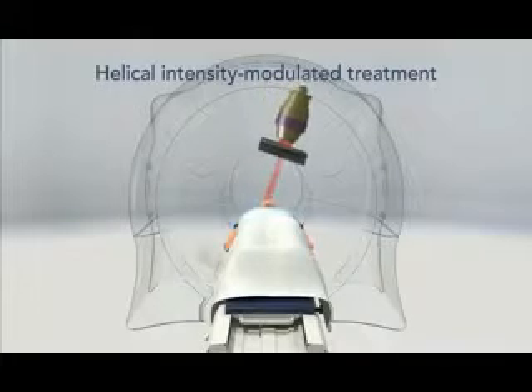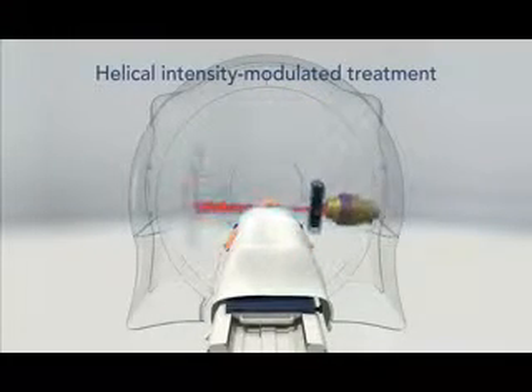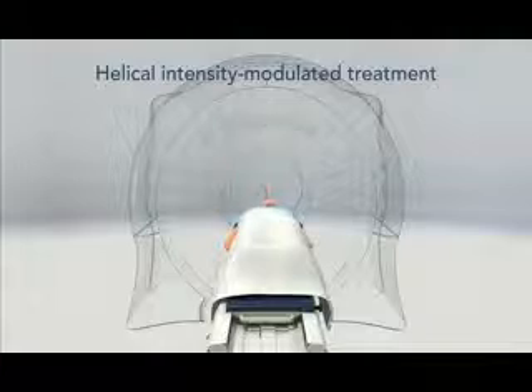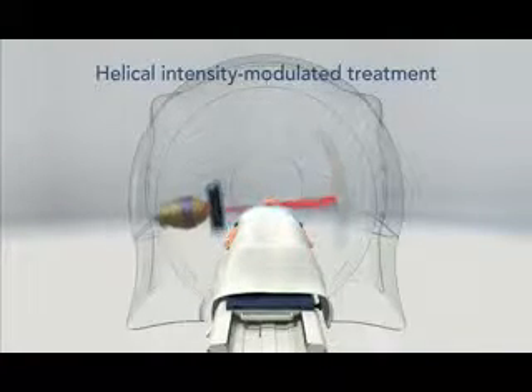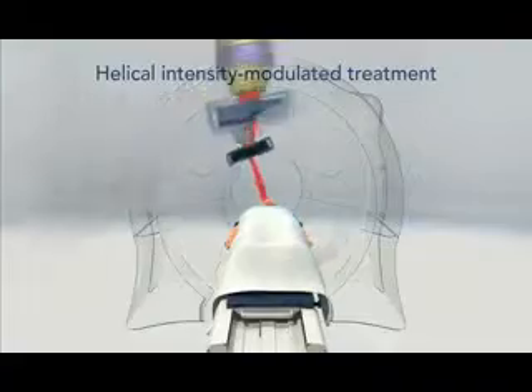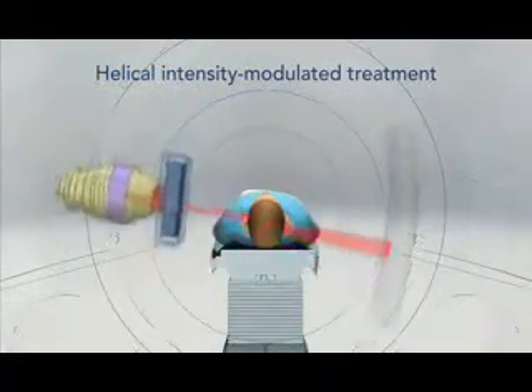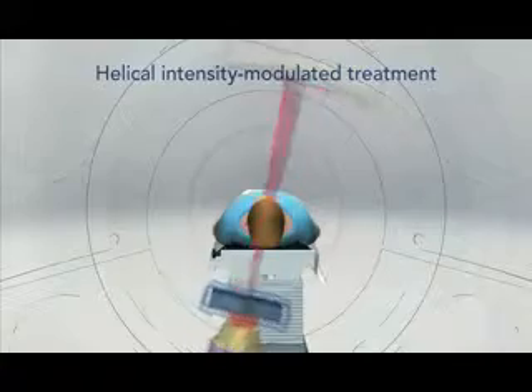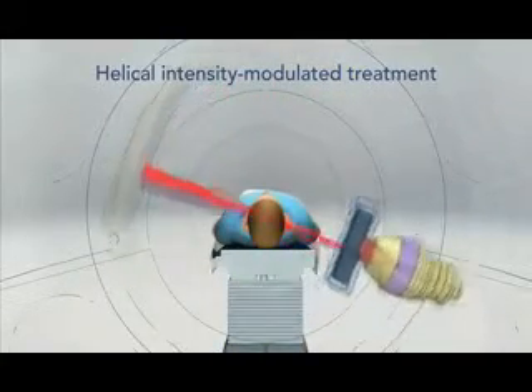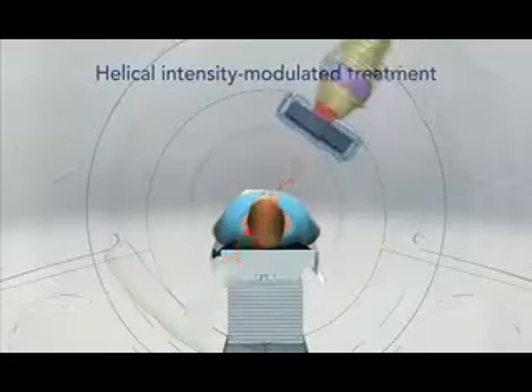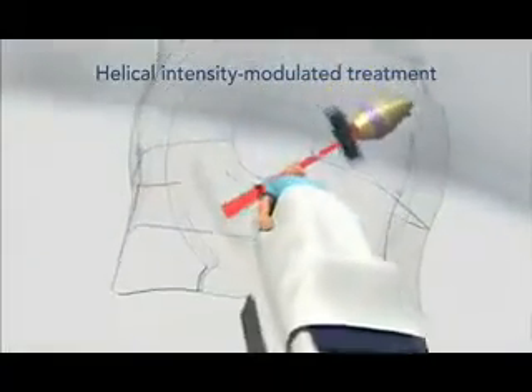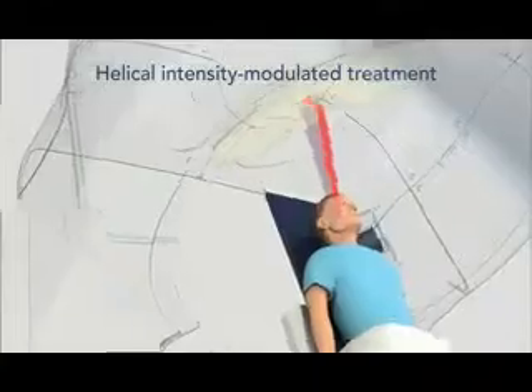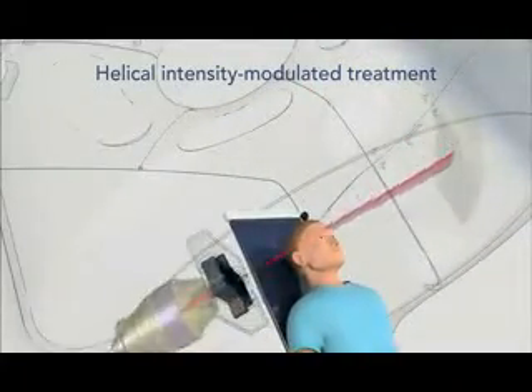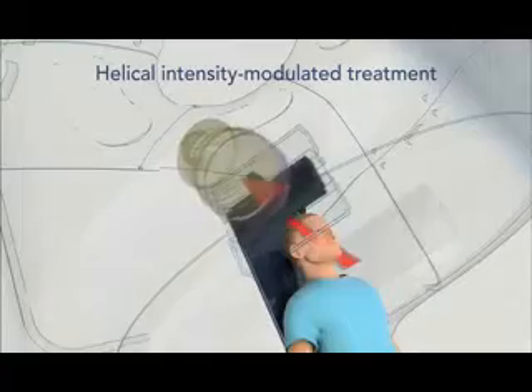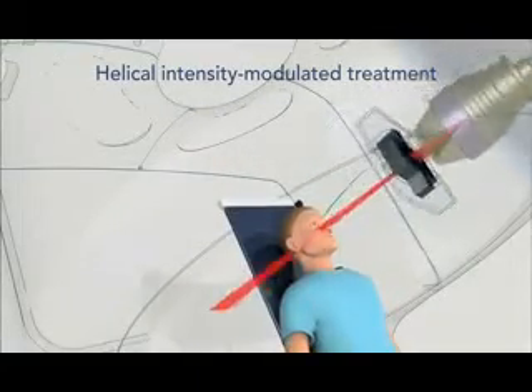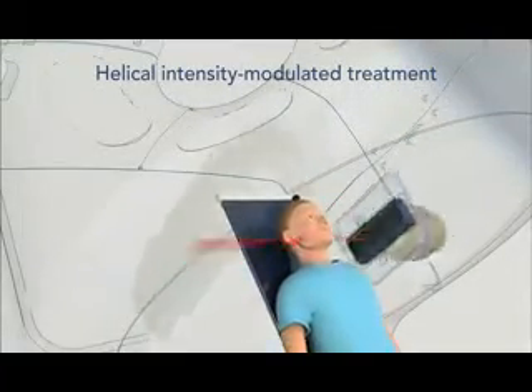For treatment delivery, the same helical rotations of the X-ray beam source are used. This time, however, the intensity of the beam is changed rapidly during each rotation, according to the shape of the tumor, using thin tungsten leaves that block or unblock the beam. The 64 leaves in our unique binary multileaf collimator create tens of thousands of optimized 6 mm wide beam elements known as beamlets. This unique combination of a helically rotating beam source and beamlet-based delivery is what distinguishes a TomoTherapy treatment from other forms of intensity-modulated radiotherapy.